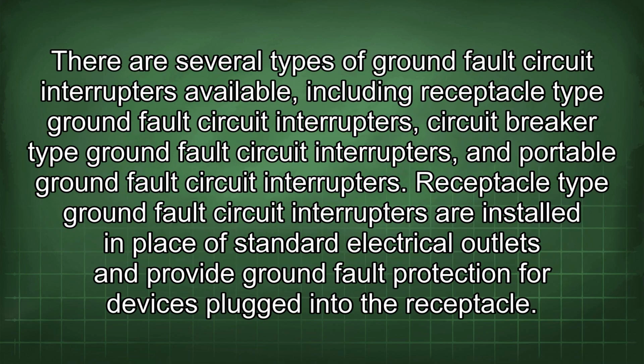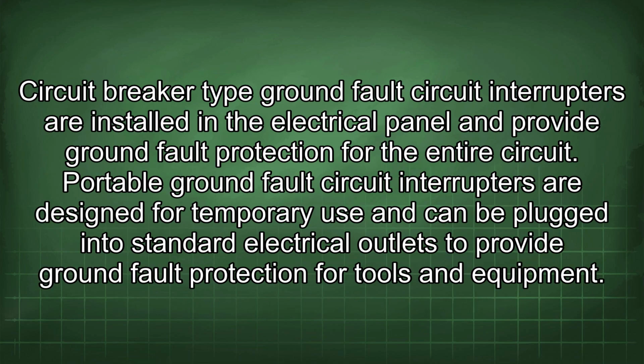There are several types of ground fault circuit interrupters available, including receptacle-type ground fault circuit interrupters, circuit breaker-type ground fault circuit interrupters, and portable ground fault circuit interrupters. Receptacle-type ground fault circuit interrupters are installed in place of standard electrical outlets and provide ground fault protection for devices plugged into the receptacle. Circuit breaker-type ground fault circuit interrupters are installed in the electrical panel and provide ground fault protection for the entire circuit. Portable ground fault circuit interrupters are designed for temporary use and can be plugged into standard electrical outlets to provide ground fault protection for tools and equipment.